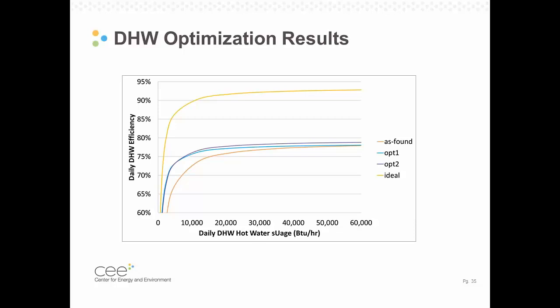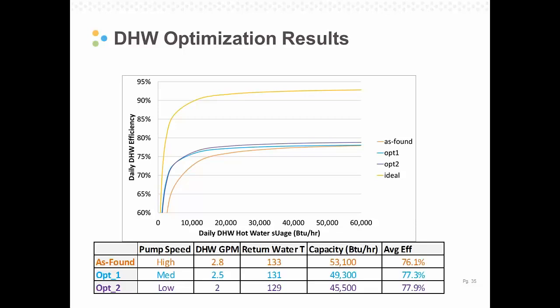And the thing you can see on this chart is, in gold is sort of the optimal efficiency. That's essentially what a condensing tankless water heater would have, where you can see about 94-95% efficiency. In the orange at the bottom of the slide is what our as-found water heater was doing. And we went through and reduced the flow rates, did some temperature modifications, and you can see we saw some benefit, but not a huge benefit.